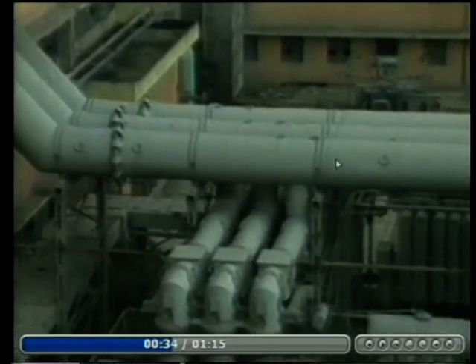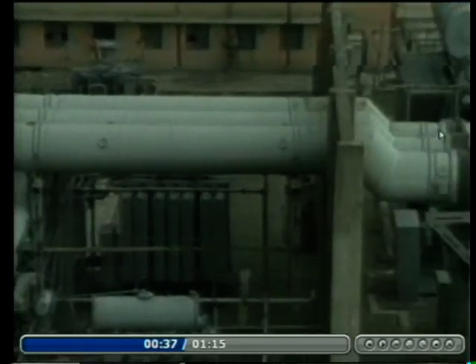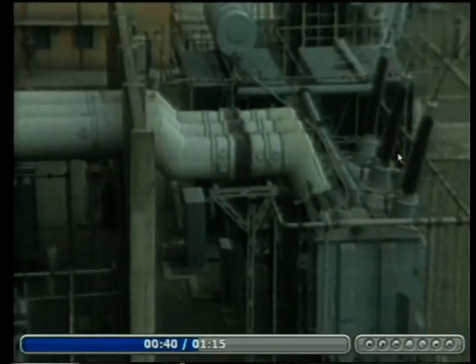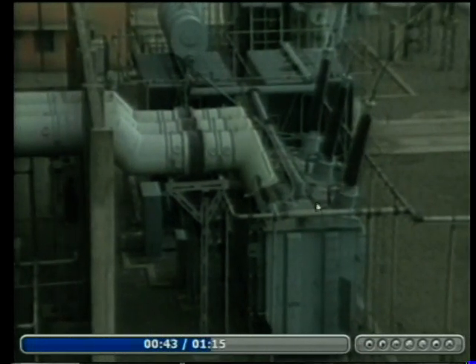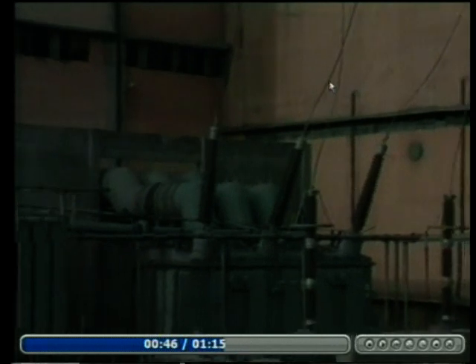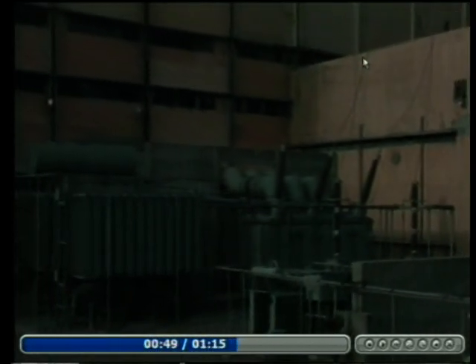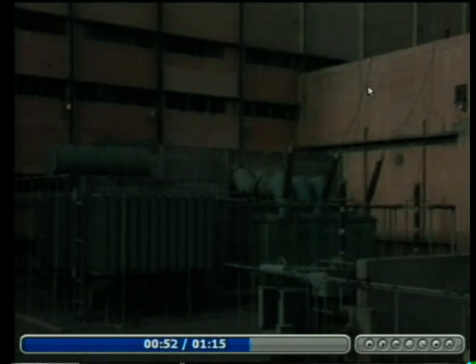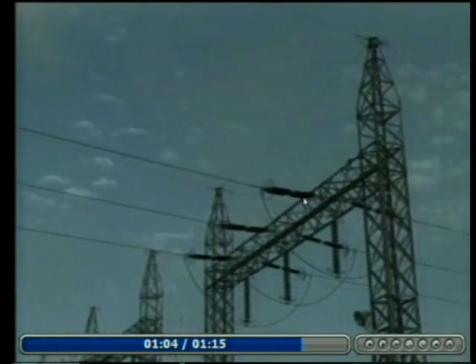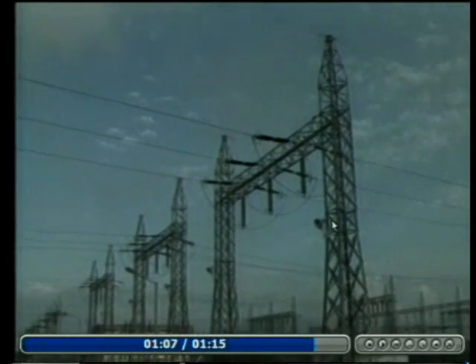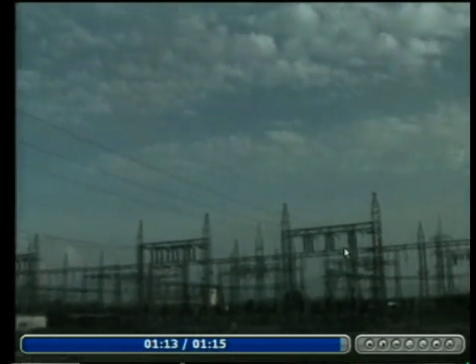Now, it is carried to the power transformer where it is stepped up to the required voltage. So, low voltage here, and here is the high voltage. This high voltage is connected to the bus bar, the common bus bar, you can see it. This is a common bus. How is it connected? You can see, by using ACSR conductors. Now, from these bus bars it is fed to the different load centers by using transmission lines.